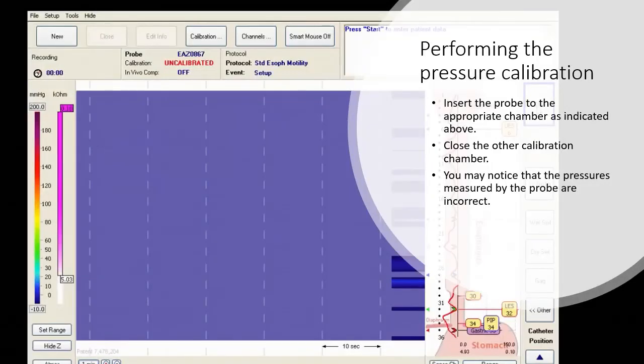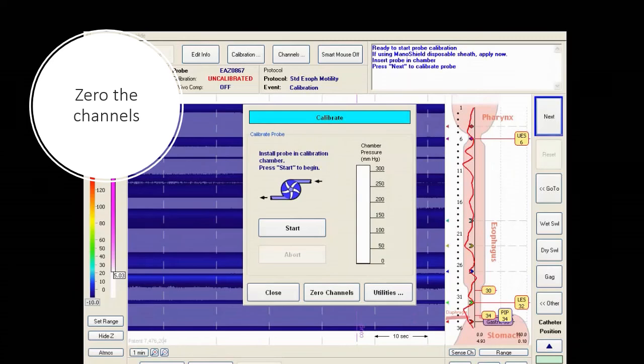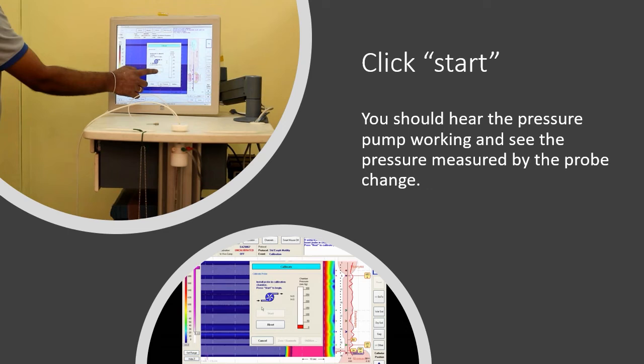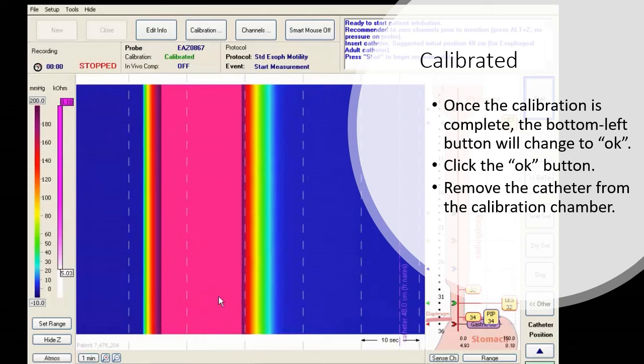To perform the pressure calibration, insert the probe to the appropriate chamber as indicated above. You also need to close the other calibration chamber. You may notice that the pressures measured by the probe are incorrect. First, zero the channels by clicking the Zero Channels button. Then, click the Start button. You should hear the pressure pump working and see the pressure measured by the probe change. Once the calibration is complete, the bottom left button will change to OK. Click this OK button and then remove the catheter from the calibration chamber.